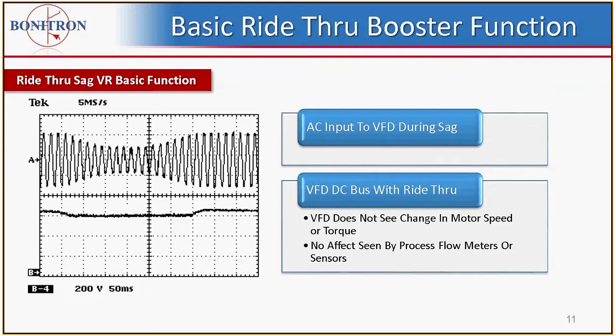still sagging, but the DC bus has only a momentary dip before the ride-through reacts, but the drive does not even see the change from utility power to ride-through. So there's no change in speed or torque of the motor that's running the process.